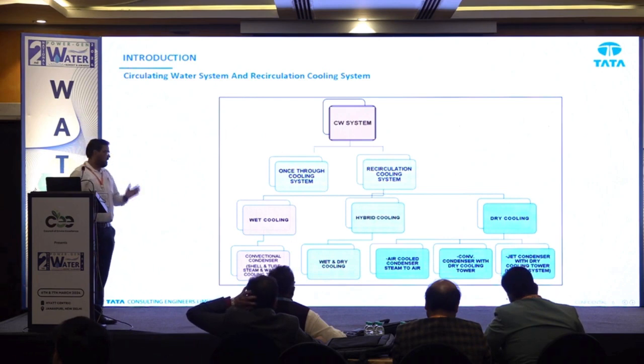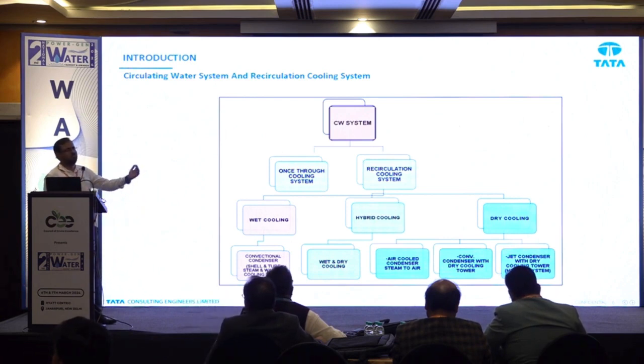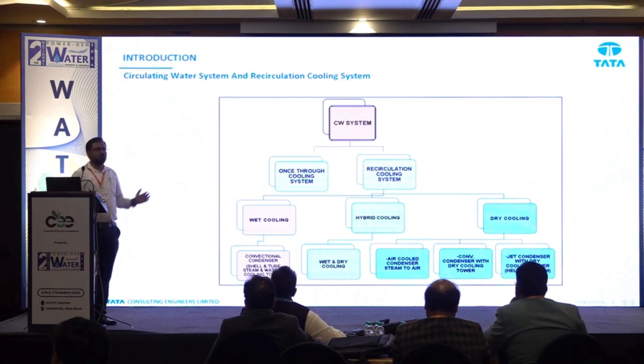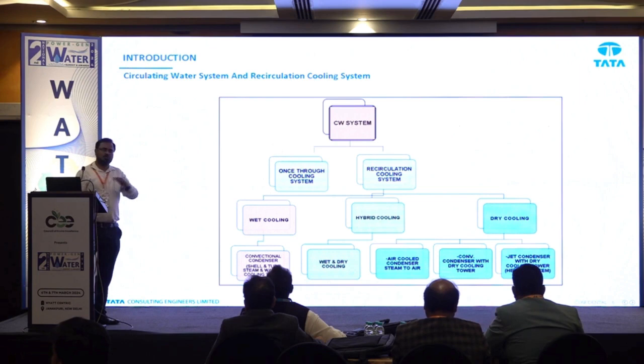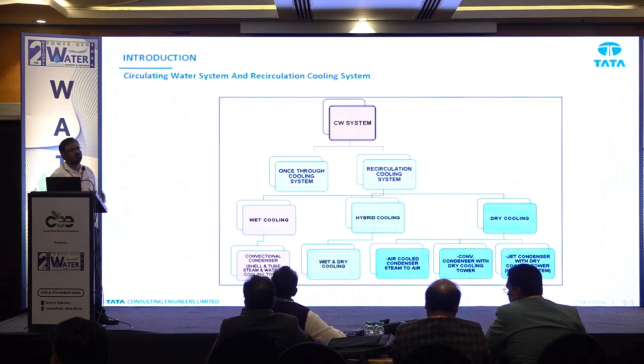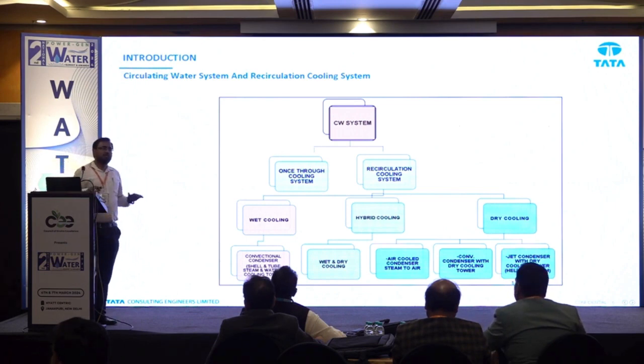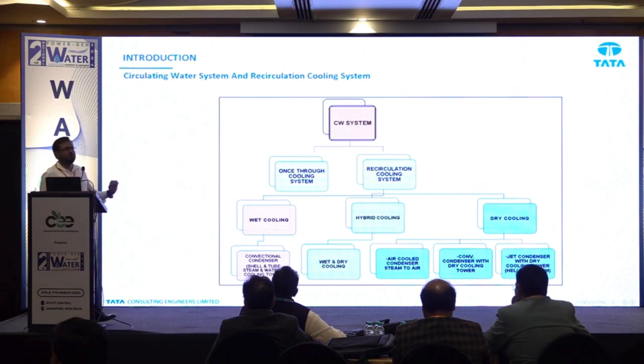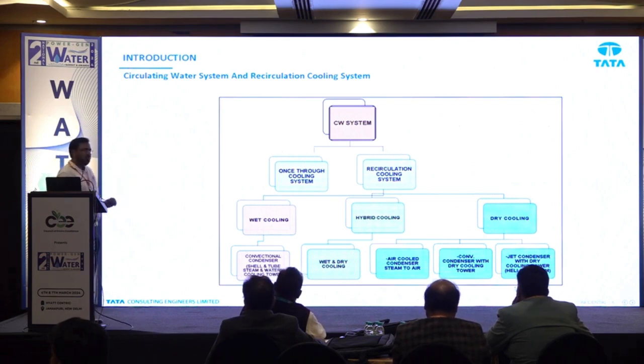So if it is available, where makeup can be done 24 by 7 throughout the year, then the wet cooling system is good because of the thermal efficiency, with 7% higher power output, less CO2 emission, and lower capex compared to the air cooled condenser. However, the air cooled condenser is also used in many places. Even NTPC has explained that it is installed in Jharkhand and other places successfully, where water scarcity is extremely high and there is no chance of going for a wet system. It is very much feasible to get the dry cooling system, no doubt about it. But where moderate water is available, the wet cooling system is more feasible because thermal efficiency is high and capex is also less compared to the dry system, and other technical aspects are also favorable for the wet condition.